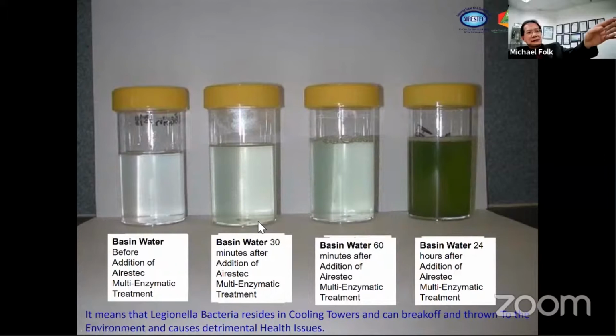30 minutes later, you see it start to change color. 60 minutes later, it gets darker. And 24 hours later, you see the color is very dark. This is to show you that Legionella bacteria resides in cooling towers, and they can break off at any time and get thrown into the environment, into the air and so forth. And it continues, it's like a factory to churn out Legionella bacteria.